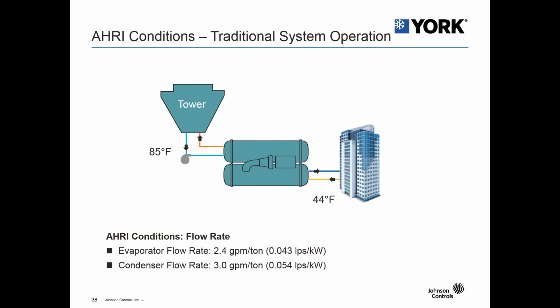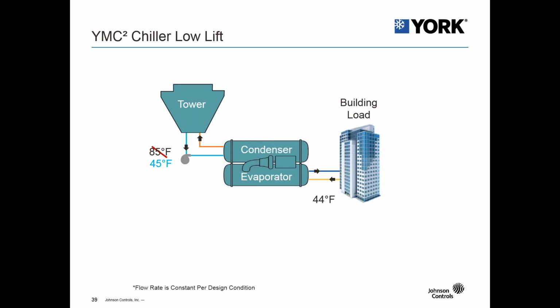So let's take a look at just how the traditional system's set up. So typically you would have an AHRI design chiller with an evaporator flow rate of 2.4 GPM per ton and a condenser flow rate of 3 GPM per ton. And your design point would be 85 degrees entering condenser water temperature with a supply of 45 degrees on the chilled water, or 44 degrees on the chilled water loop.